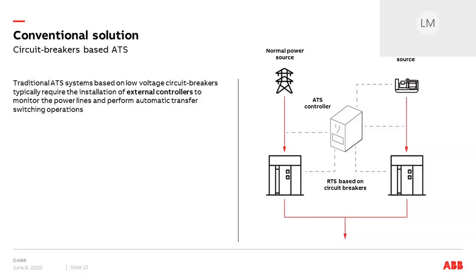Both air circuit breakers and molded case circuit breakers are suitable for ATS applications according to the technical requirements of the installation. Accessories for remote operations, mechanical and electrical interlocks, as well as communication between devices are also required. The external ATS controller is typically responsible for voltage and frequency sensing and is able to detect abnormal conditions like voltage unbalances or phase losses. It also allows the setting of parameters like time delays and provides a basic human-machine interface to monitor system operations and conditions.